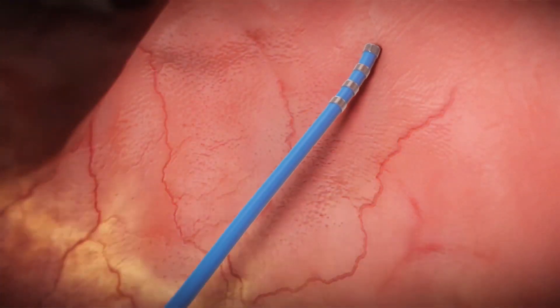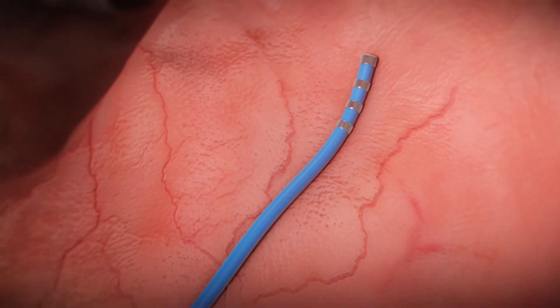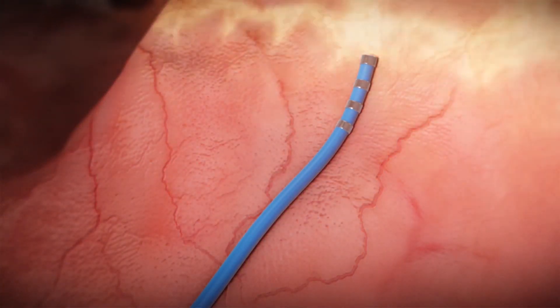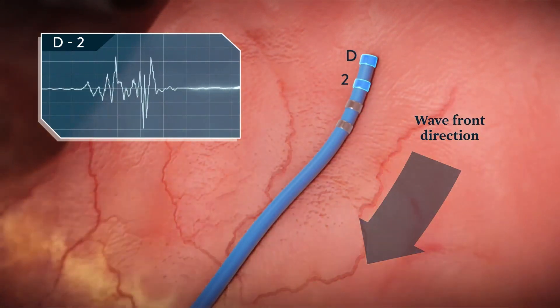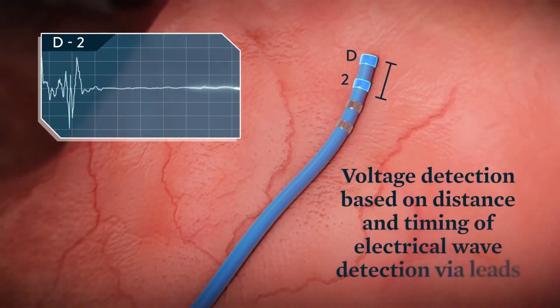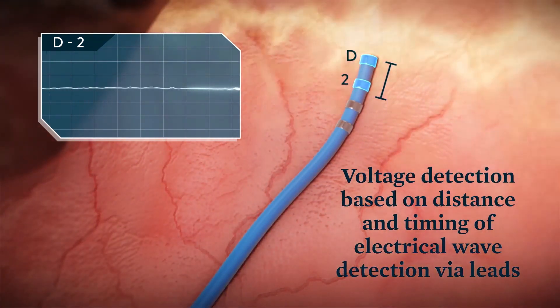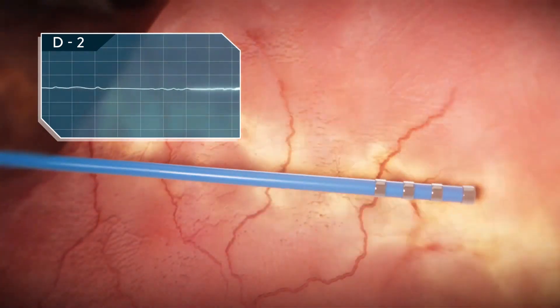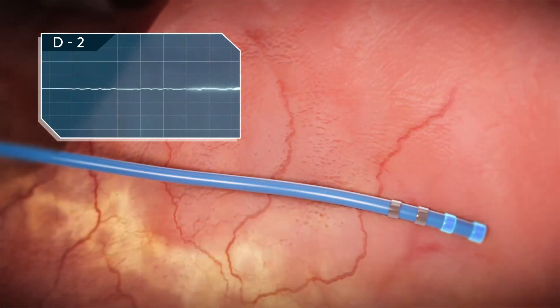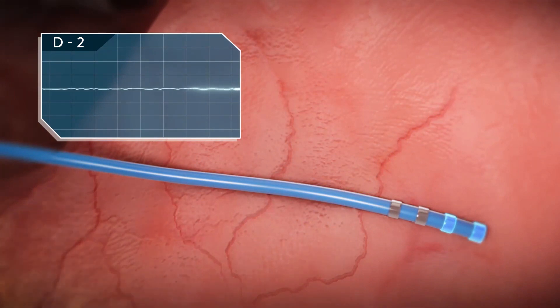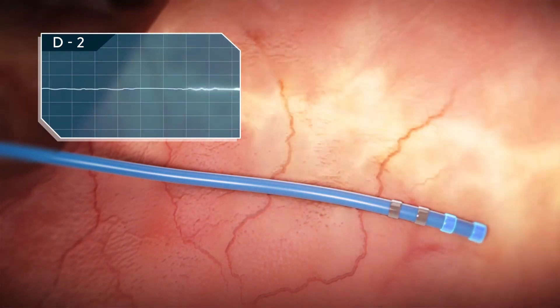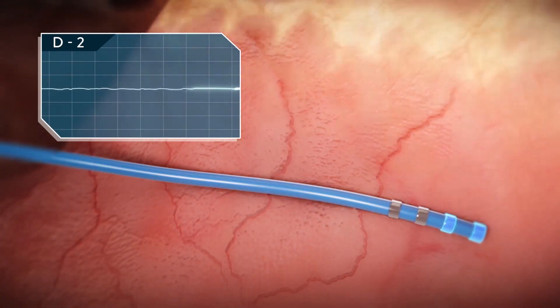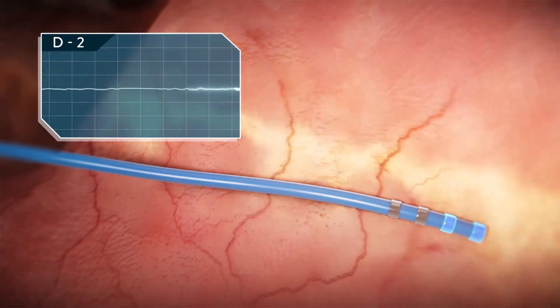Electrophysiology catheters are typically made of woven Dacron, a woven copolymer, polyurethane, or plastic. The electrodes are usually silver or platinum-based. Electrode pairs are usually closely spaced approximately two millimeters apart, with varying amounts of space between pairs. Typical diagnostic catheters will have four electrodes — a proximal pair and a distal pair spaced approximately five millimeters apart — and a fixed curve at the distal end. The catheter is rotated at its proximal end by the physician as it is inserted from a vascular access site and advanced under fluoroscopic imaging, precisely positioned within the heart to record the desired signal.